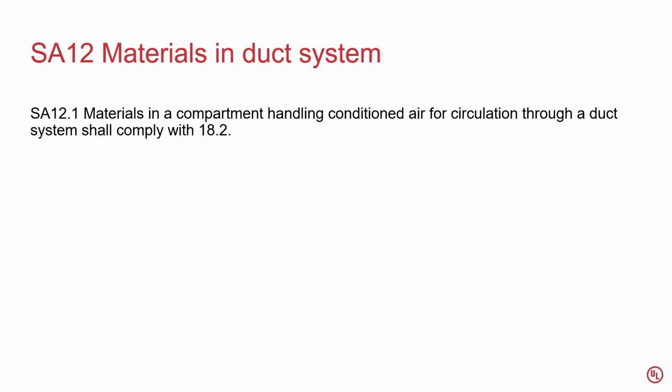So we would do this testing to UL 723, and that gives you what they call a 25/50 rating, a smoke developed type rating. So we would require that anything non-metallic, up and above that UL 1598 standard, would have to meet those requirements, so they don't smoke and create a panic hazard within that building structure. So, next slide.